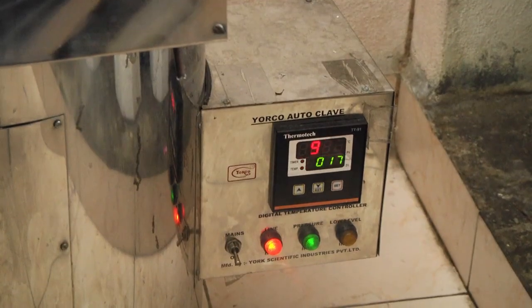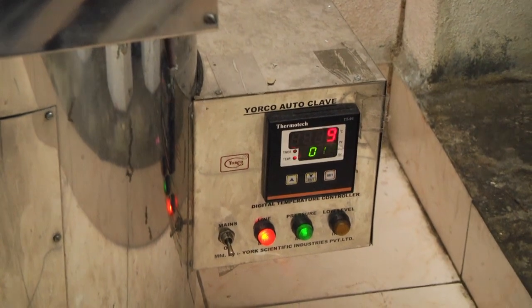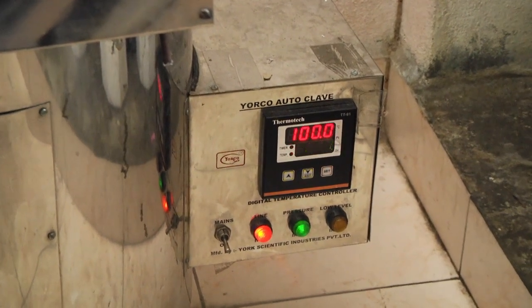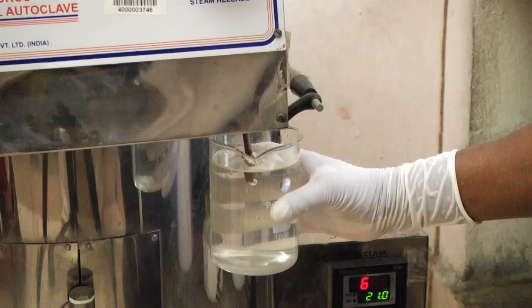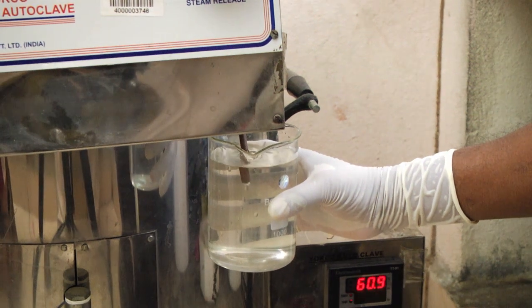Heat the autoclave. If using an electric autoclave, switch on the power to maximum setting. Allow the correct length of time for all the air to be expelled as instructed by the manufacturer. Check whether all the air has been expelled.